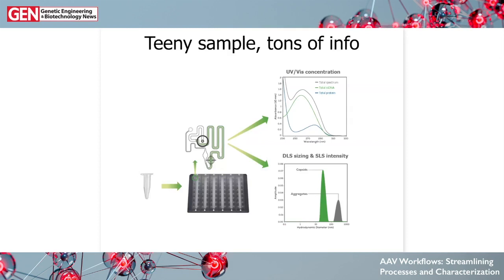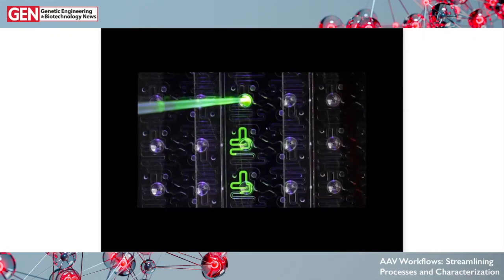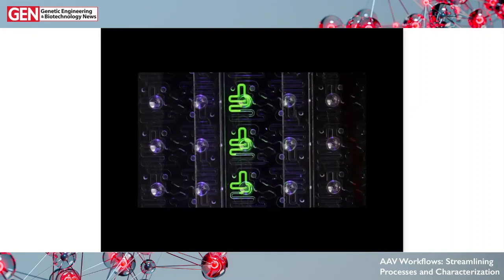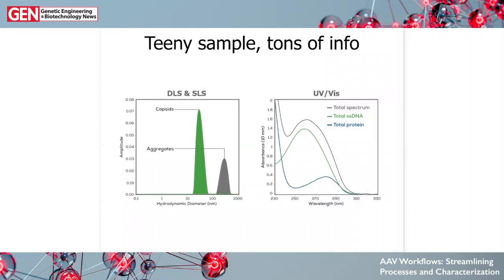Getting data from such a small sample volume starts with Stunner's consumable 96-well plate. Each well is a microfluidic circuit that lets you use just two microliters of sample to get information from two technologies: UV-Vis for concentration and DLS for sizing. SLS intensity data is also read during a DLS experiment. The plate can be used to read one sample or all the way up to 96 samples at a time. Stunner's AAV Quant application then combines those two pieces of powerful information into a full story about your AAV.